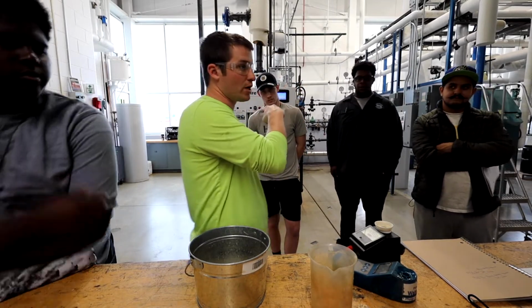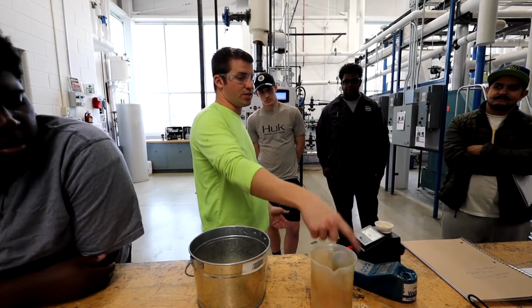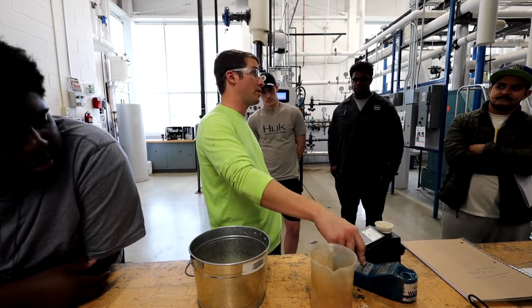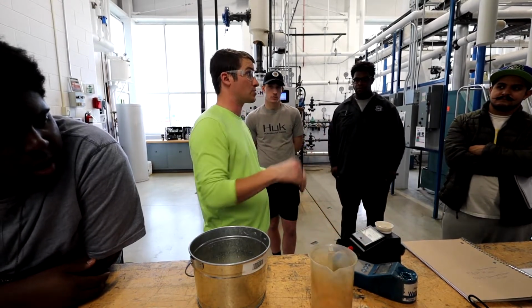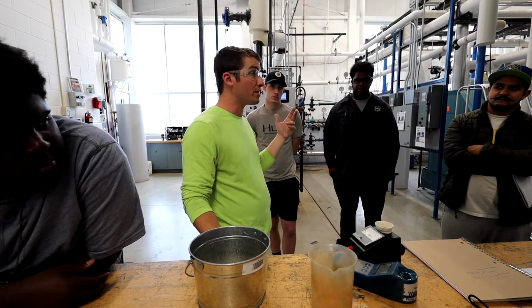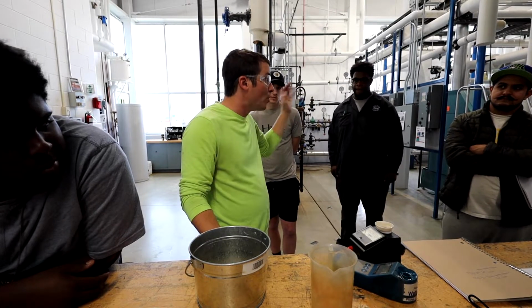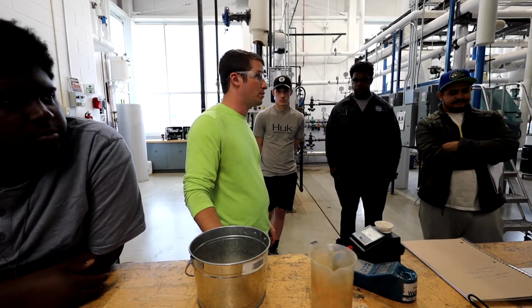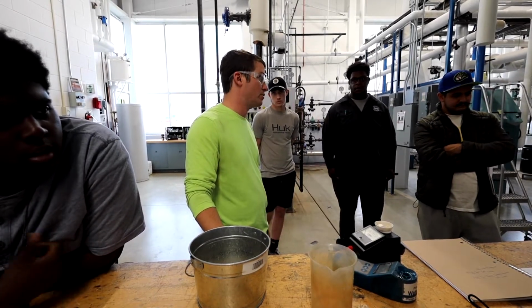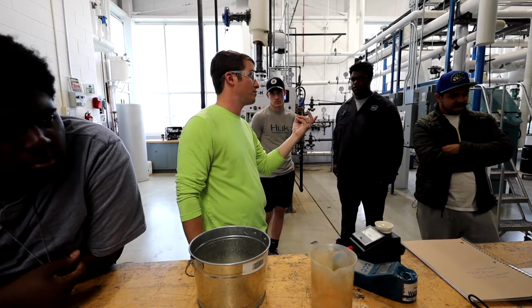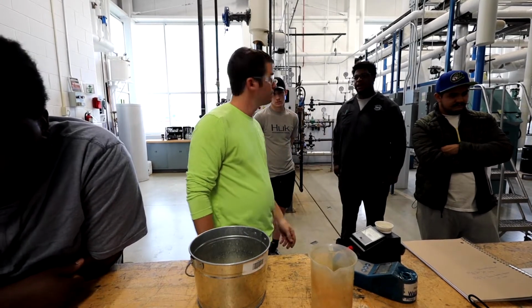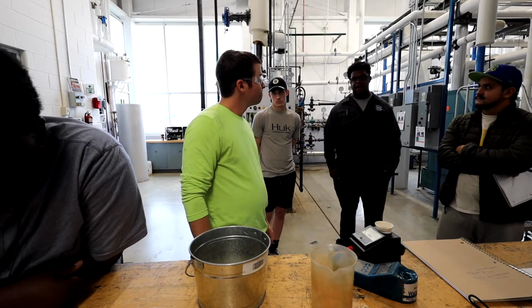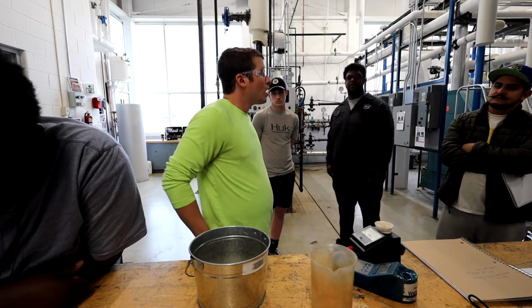So if we're 300 coming in and we have 60, 66, let's do 50 for easy math, right? So that's 6 times less. So that tells me, if I did the math, you're getting 80+% condensate return, which is pretty good, right? You're probably getting 90+% condensate return. The chemicals are gonna add a little bit of conductivity to the water when they get added. So is that the ideal range for condensate return, or is that a question for CC?